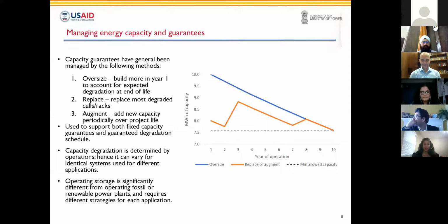But what we're seeing more commonly is a replacement or augmentation strategy, where the developer replaces degraded racks or adds new racks to boost the system's capacity at fixed points in the future. This is often more cost effective for larger systems, because we can make use of projected battery cost declines and bring down the whole system's cost at year zero.